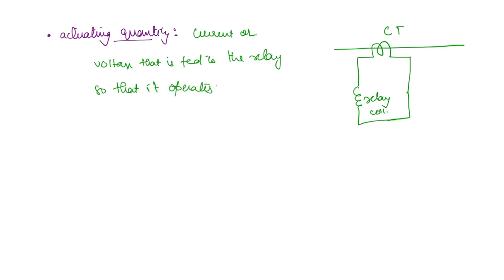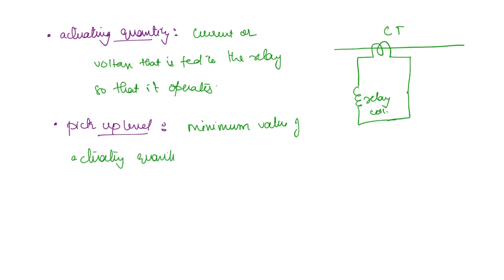Next, the pickup level. Under normal working condition, there is no current in the CT. But if the current exceeds a certain value, only then will there be a current in the CT. So that is the pickup level: the minimum value of actuating quantity above which the relay operates. So this is the pickup level.